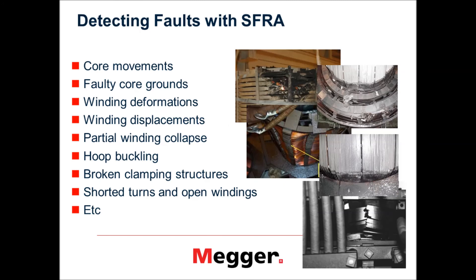With this SFRA method, you can pick up various different kinds of problems that may go unnoticed from other electrical tests. Problems like displacement of the windings, winding deformation, hoop buckling — which is one of the case studies we will talk about. Other problems like broken clamping structure, where if you don't have enough pressure on the winding, the winding would get loose. Problems related to the core of the transformer — shifting of the core, shorted laminations, or the core ground not connected properly. All those kinds of things you would be able to pick up with this SFRA test.